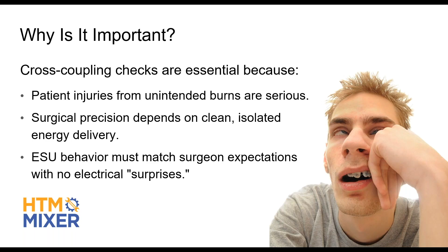Okay, yes. You could, that's where it really comes into effect. We're not doing that when we're checking it, but yes, that's where it would. You could have something laying there or somebody doing something else with it that, yeah, you don't want anything coming out of that. Or what we do is we know that's got to be on less than 150 milliamps. And if we check it and it's somewhere in between, in that case where it was 49, I think, it was somewhere halfway, something like that, but it's well within the limits. But yes, exactly what you're talking about.